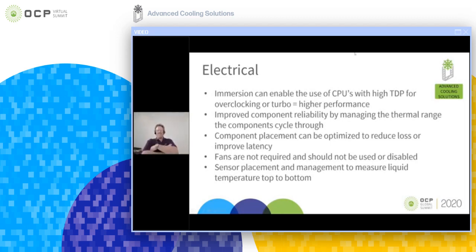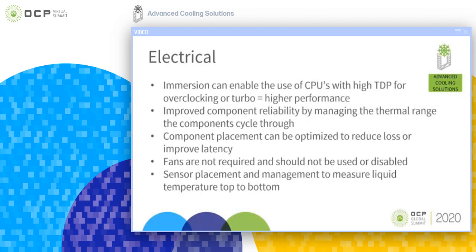Hey, Rolf, thank you very much. Yeah, I'm going to cover a few slides on the electrical, a few key points. Obviously, with immersion, it will enable the CPU to really extend its ability to turbo, for higher performance that you might not be able to get in your conventional forced air cooling. Reliability is a key factor: as chips like CPUs migrate from a higher thermal limit and back down to a lower limit, that tends to degrade the reliability of components. So being able to manage a component like a CPU at a nominal temperature throughout its life cycle will extend its reliability.